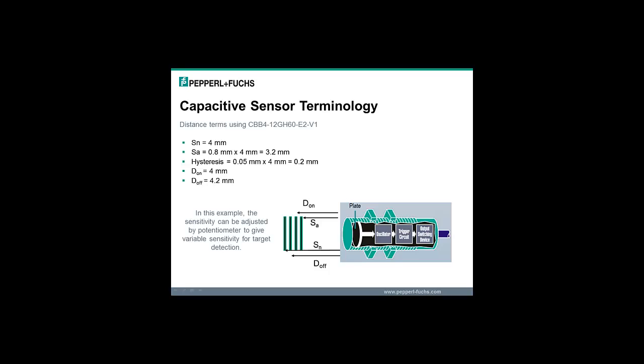Here we see an example of how the sensing definitions apply to a basic capacitive sensor. The CBB4-12GH60-E2-V1 is a standard Pepperl+Fuchs capacitive sensor with a defined sensing range of 4 millimeters. In this case, the standard sensing distance is 4 millimeters, the assured sensing distance is 3.2 millimeters, and the hysteresis is 0.2 millimeters. Since the assured distance is defined based on multiple factors including supply voltage and temperature, it is common to have a sensor that triggers at a distance greater than the assured distance. The assured distance defines the position where a sensor is guaranteed to activate only if the sensor is operated over the complete temperature range.